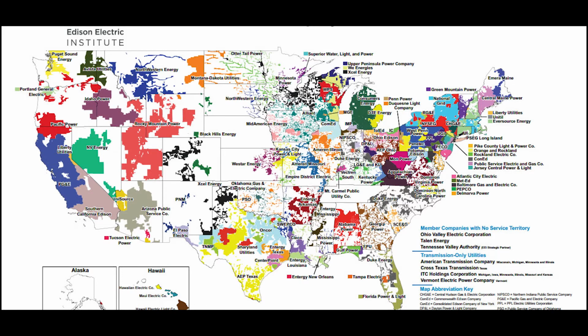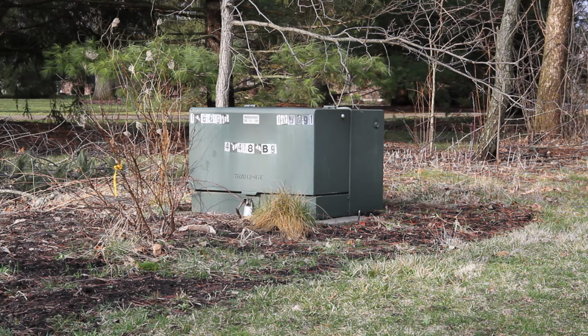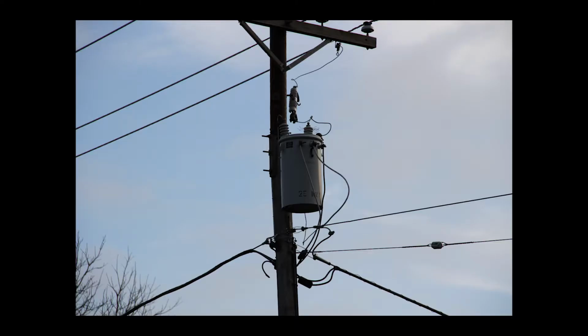The proposal assumed that all homes in the U.S. are provided with at least 1,000 amps of available short-circuit current, and that the circuit breaker would be at room temperature. Some homes in the U.S. may be served with as little as 500 amps of available short-circuit current, such as those in rural areas or in apartment or condo buildings. Even homes that have more than 500 amps of available short-circuit current at the main circuit breaker panel may have circuits installed that are fed from sub-panels, where the available short-circuit current is less due to the resistance of the wire between the main and sub-panels.